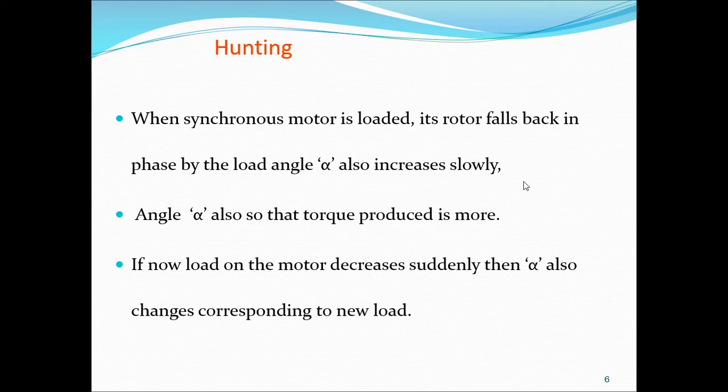When a synchronous motor is loaded, its rotor falls back in phase by a certain angle called the load angle or coupling angle alpha. As load is progressively increased, this angle alpha also increases so as to produce more torque for coupling with the increased load.